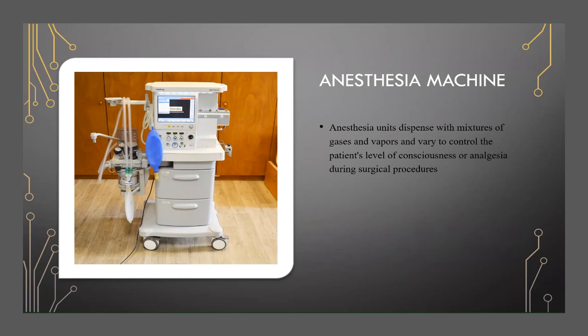Anesthesia units dispense mixtures of gases and vapors and vary or control the patient's level of consciousness or analgesia during surgical procedures. Anesthesia units primarily perform the following four functions. First of all, providing the patient with oxygen, and mixed gas mixtures in addition to O2, which may contain vapor, anesthetic, nitrous oxide, other medicinal gases, and air. Facilitate spontaneous or controlled ventilation with the help of these gas mixtures, reducing, if not eliminating, anesthesia-related risk to the patient and the clinical staff.